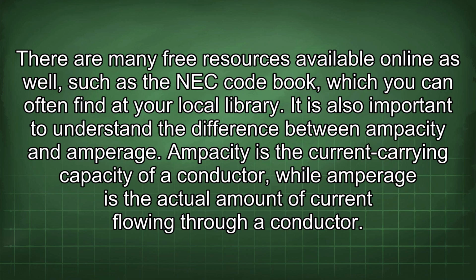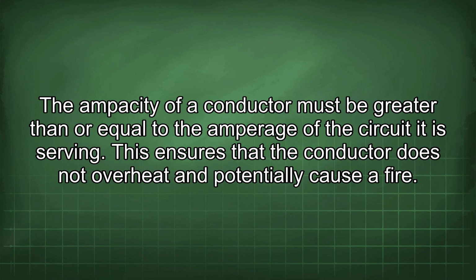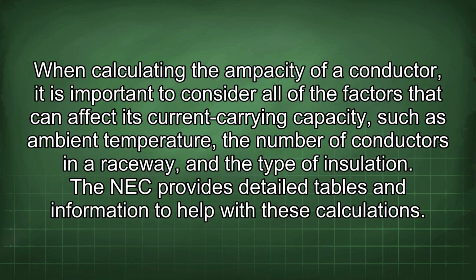Ampacity is the current carrying capacity of a conductor, while amperage is the actual amount of current flowing through a conductor. The ampacity of a conductor must be greater than or equal to the amperage of the circuit it is serving. This ensures that the conductor does not overheat and potentially cause a fire. When calculating the ampacity of a conductor, it is important to consider all of the factors that can affect its current carrying capacity, such as ambient temperature, the number of conductors in a raceway, and the type of insulation. The NEC provides detailed tables and information to help with these calculations.